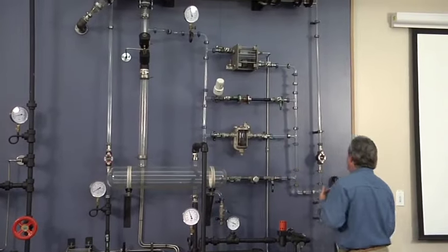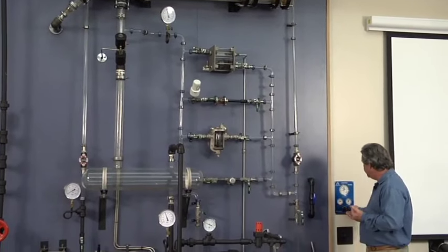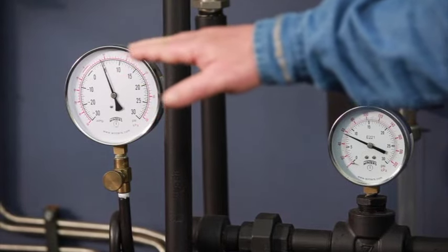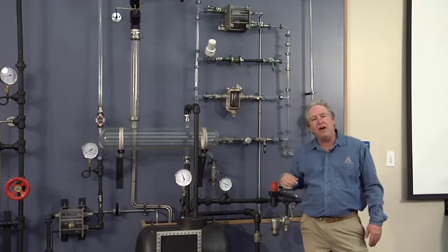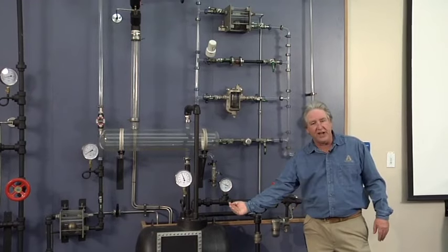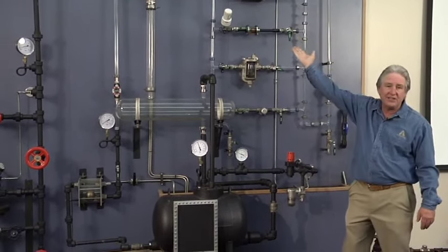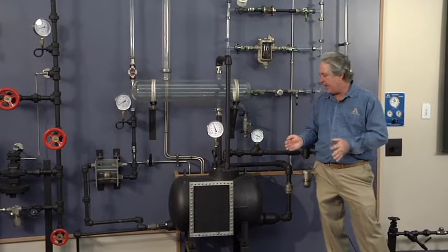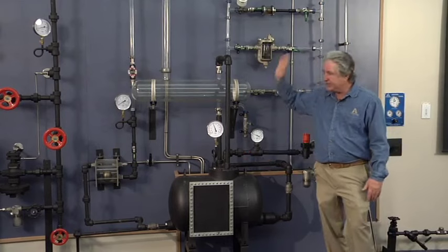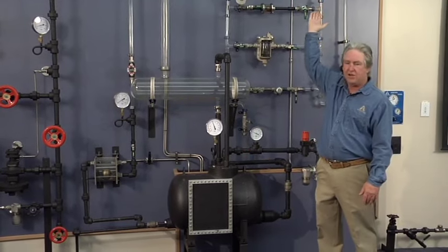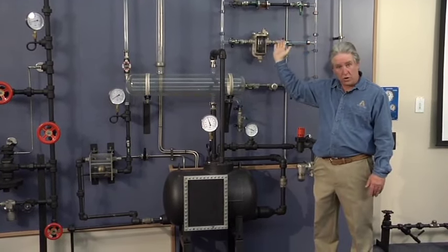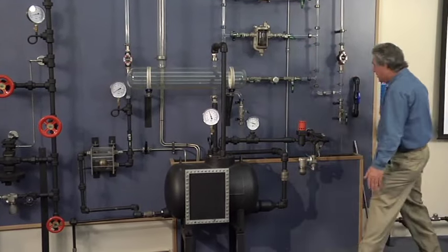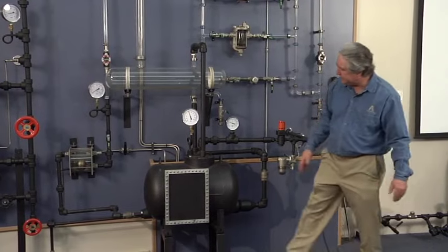What I'm going to do now is slowly modulate the steam control valve to decrease the amount of steam flow to the exchanger, because we're going to drop this outlet pressure, and we want to demonstrate to you that this system allows the exchanger to run at either 5 pounds, 100 pounds, or in a negative pressure. Because there goes the pump. I believe it just cycled.